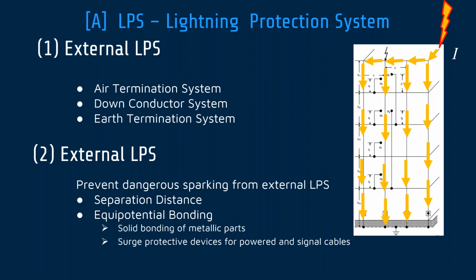And again, from the data that we can access, it will tell us how often we have multiple lightning strikes where our surge arresters need to be able to handle more joules. If it can't, if we see statistically our surge arresters are failing, then rather than upping the knee point, well, it comes back to the kiloamp rating of the surge arrestor.